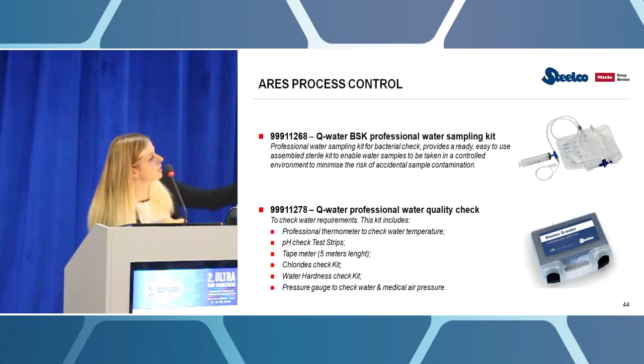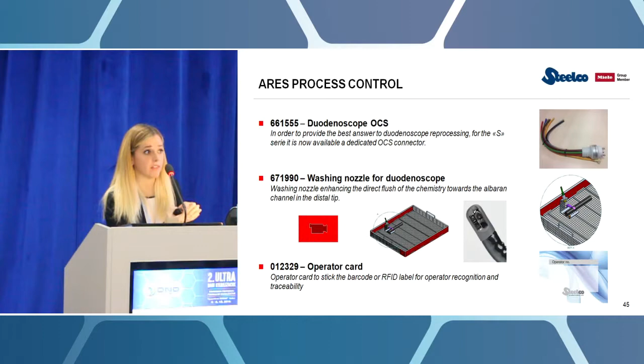This is what I was mentioning earlier, the special support for the duodenoscope. As you can see, you can place it in every single washing cart we have available, and it has a specific nozzle that flushes the distal part with the elevator channel of the duodenoscope to provide a better water pressure exactly on the elevator channel and to be able to clean that thoroughly.